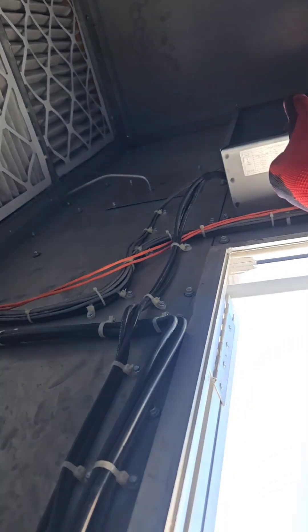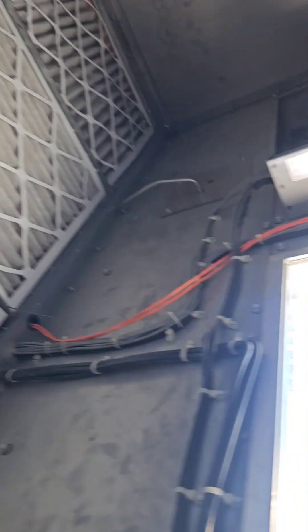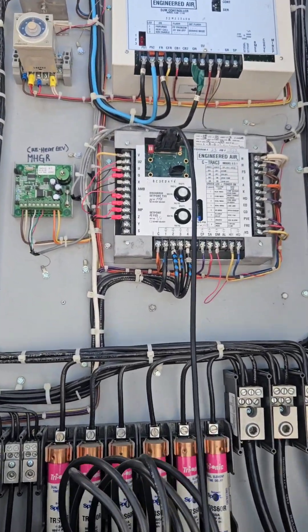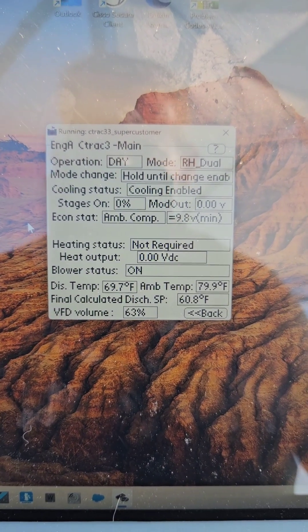Just replaced that VFD up in there and we have a functioning heat wheel. It was a pain in the butt, that VFD right there. Connected to the C-Trac controller and there we go.